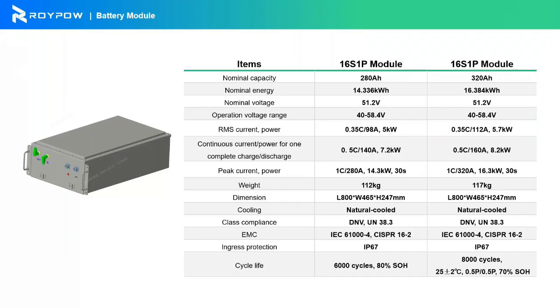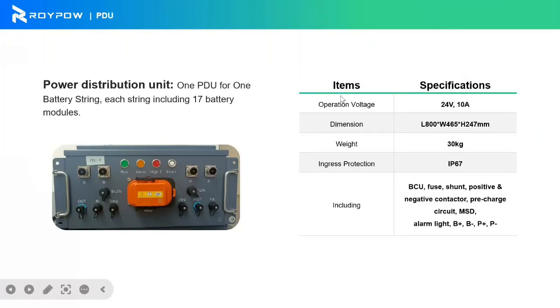Each battery module is 51.2 volts. And this is the PDU, power distribution unit. We use one PDU for one battery string, and each string can include 17 battery modules, which means one PDU can manage 17 battery modules. The PDUs also have IP67 protection, with the BCU, fuse, shunt, positive and negative contactor, pre-charging circuit, MSD, alarm light, etc.